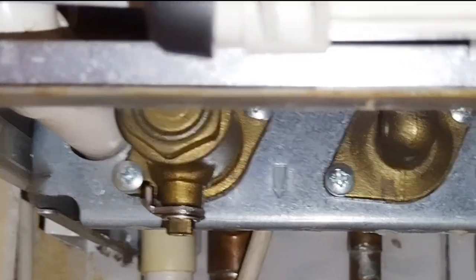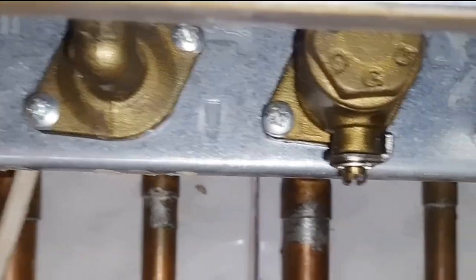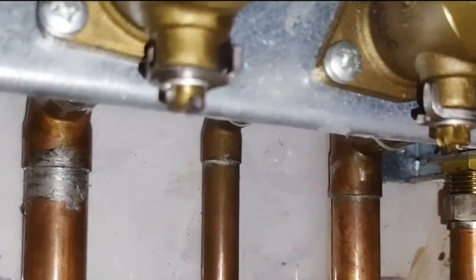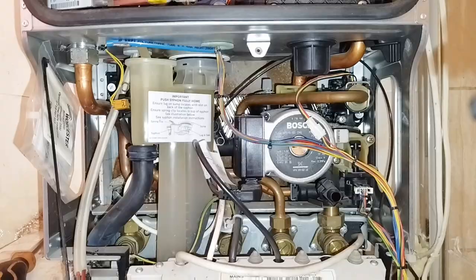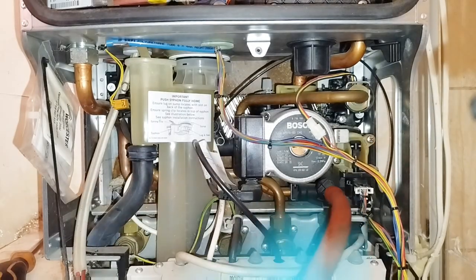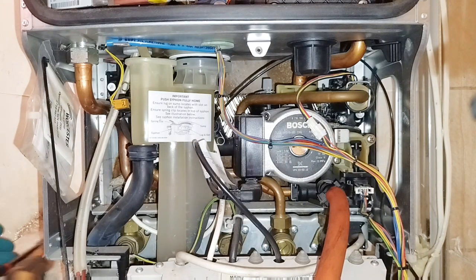And you can see that it will drip mostly from the right hand side. Alright, so to start with, we will isolate all the valves. We'll leave the gas valve on, the heating flow and return valves isolated, cold water inlet isolated, and a drain hose pipe connected to the drain point, and we've opened the drain valve up.